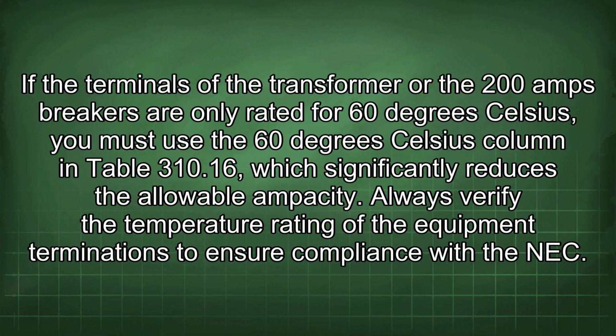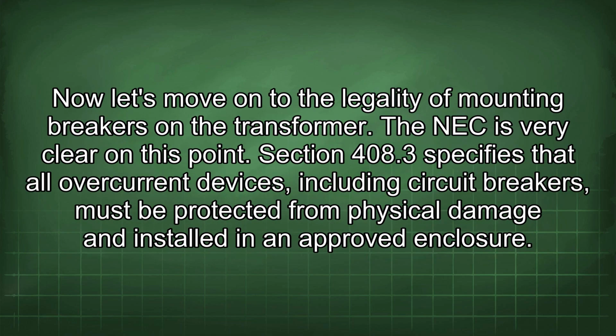If the terminals of the transformer or the 200 amp breakers are only rated for 60 degrees Celsius, you must use the 60 degrees Celsius column in Table 310.16, which significantly reduces the allowable ampacity. Always verify the temperature rating of the equipment terminations to ensure compliance with the NEC. Now let's move on to the legality of mounting breakers on the transformer. The NEC is very clear on this point.